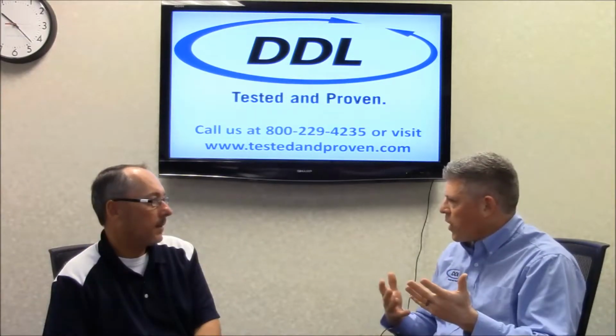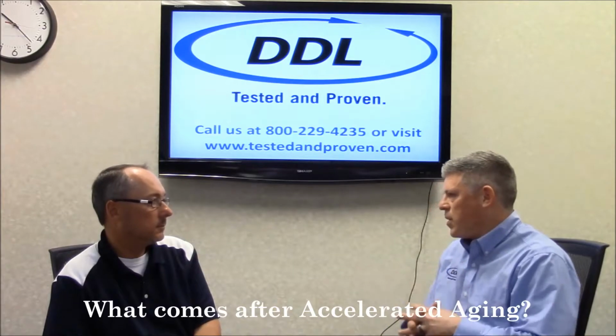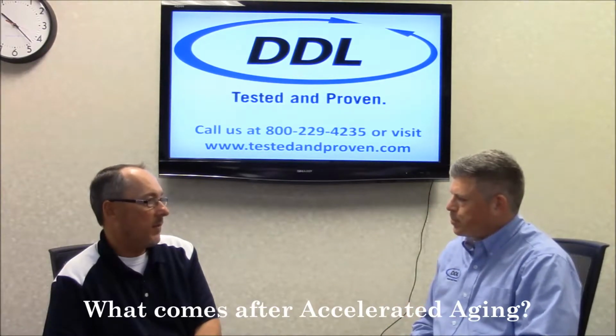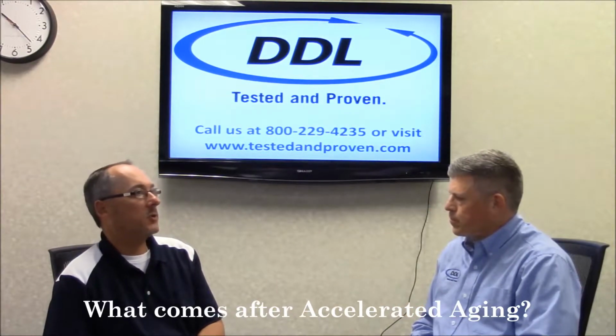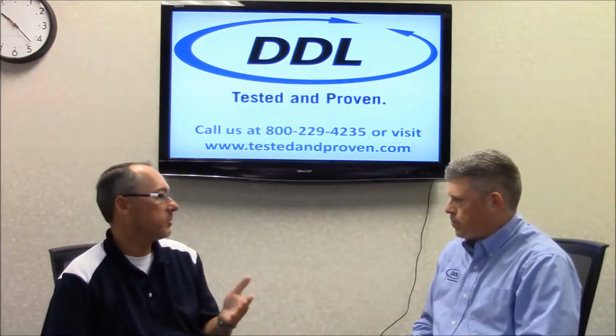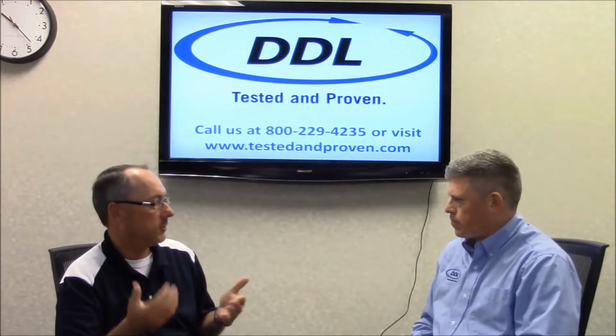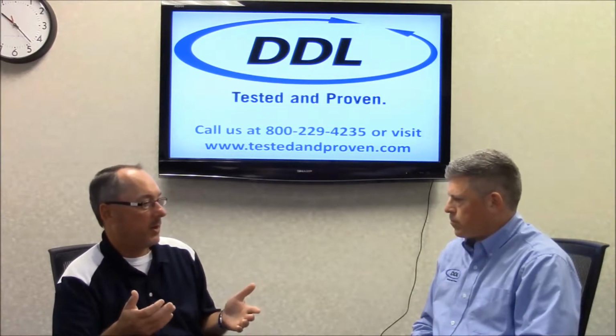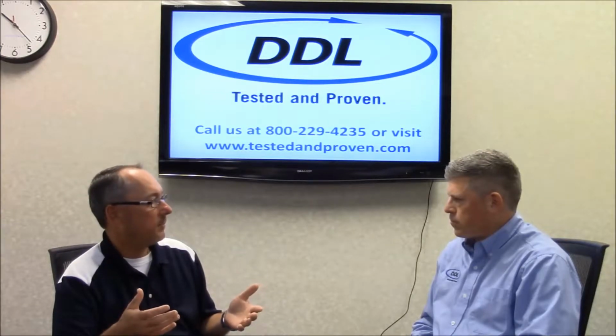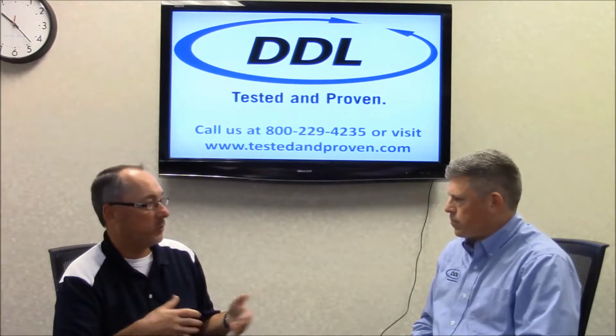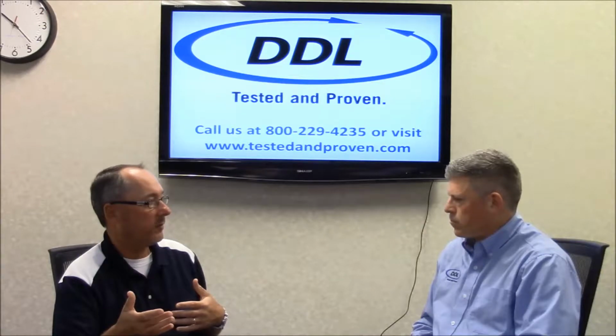So once the accelerated aging is done, what happens next? Well, I think that's another big misconception, that if you run accelerated aging, you get your expiration date, and that's not the truth. Accelerated aging is simply a conditioning step. It doesn't tell you whether you pass or fail. It's what you do afterwards that's going to tell you whether you pass or fail.